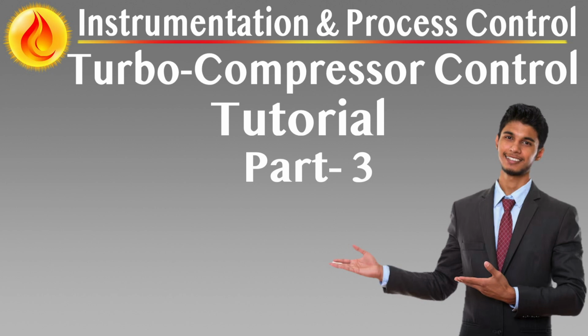In facilities with multiple turbo compressor trains operating in parallel, the Turbo Compressor Control System, TCCS, incorporates a dedicated load sharing algorithm to ensure optimal distribution of compression effort. The objective is not simply to equalize power output, but to maintain equal proximity to surge for all machines, maximizing system stability and efficiency.